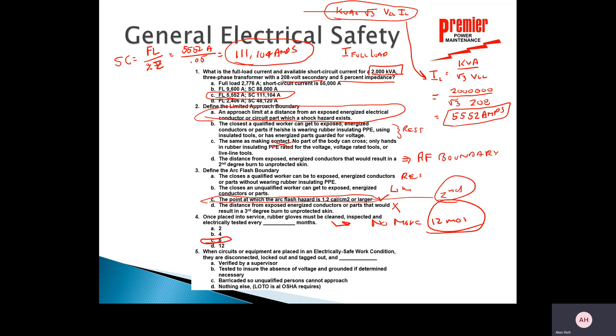When circuits or equipment are placed in an electrically safe work condition, they are disconnected, locked out, tagged out, and then verified. The full steps are: identify the equipment and where it's fed from, isolate and lock out, then test to ensure the absence of voltage, and then ground if determined necessary. The correct answer includes testing for absence of voltage and grounding if determined necessary — grounding is required above 480 volts.